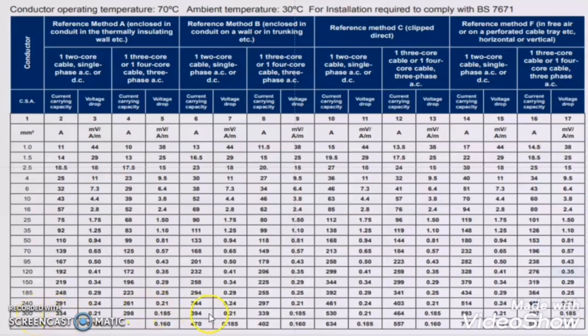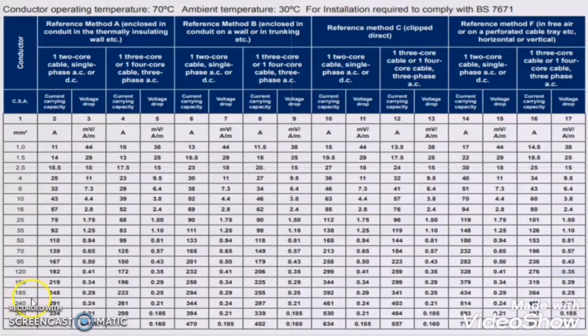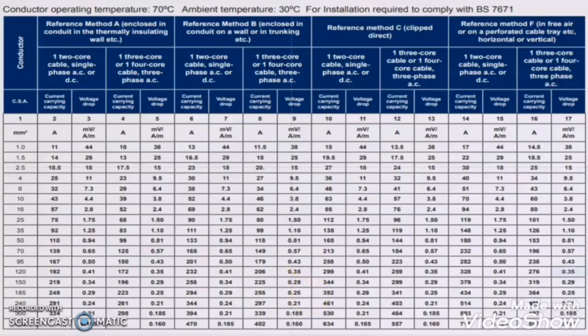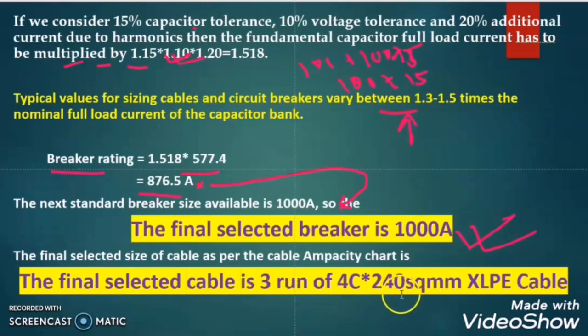We can also go for 3 runs of 300 sq mm since the current ampacity of 3 runs of 300 sq mm is also greater than 1000A. However, the ampacity chart is prepared at standard conditions of 30°C ambient and 70°C conductor temperature. In practical situations, the ambient temperature may be higher, so it is safer to use a higher cable size. The final cable size selected is 3 runs of 4-core 240 sq mm XLPE cable.